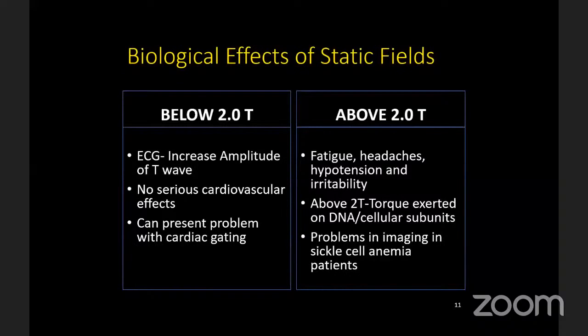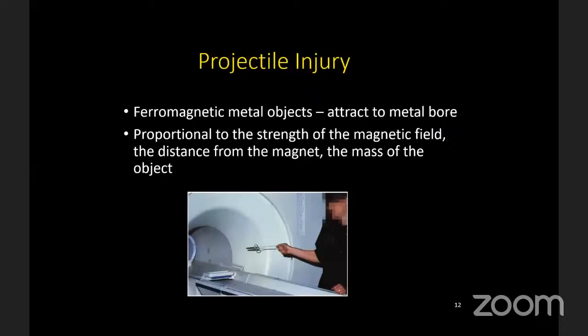The effects of the static magnetic field causing safety issues are due to the attraction of ferromagnetic material towards the magnet, which can cause projectile injuries or biological changes. If the magnetic field strength is less, there are no serious cardiovascular effects, though there may be a mild increase in T-wave amplitude. But above 2 Tesla, there have been reports of fatigue, headaches, hypotension, irritability, and problems in imaging sickle cell anemia patients. Projectile injuries are proportional to the field strength, the distance from the magnet, and the mass of the object.